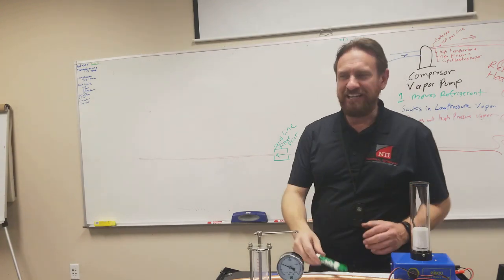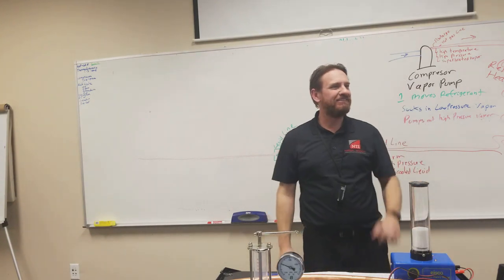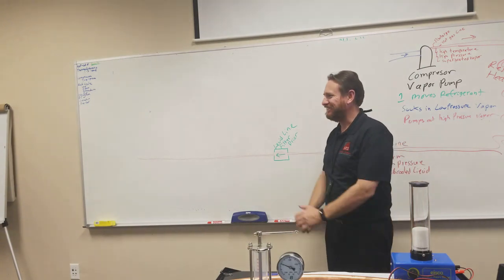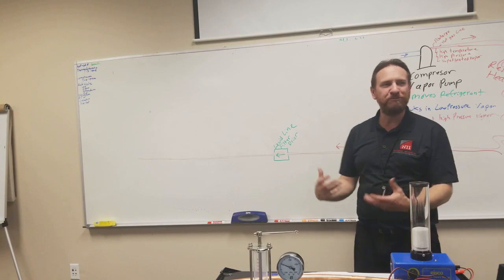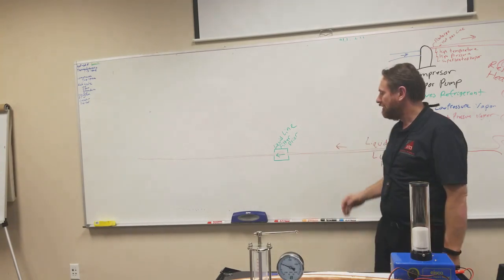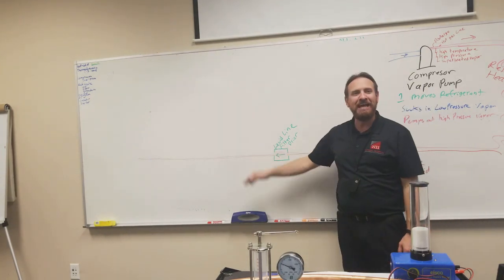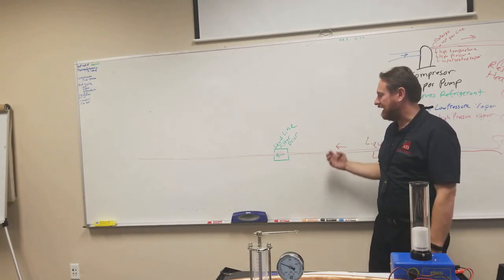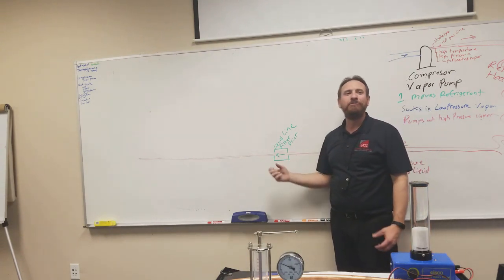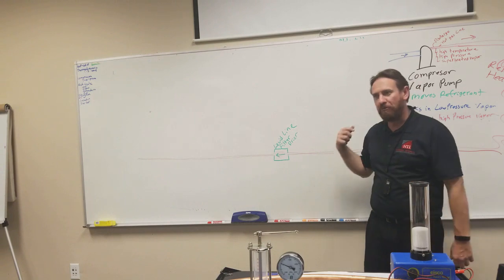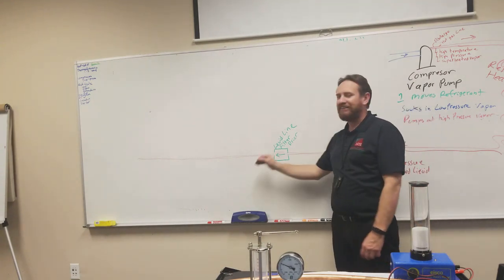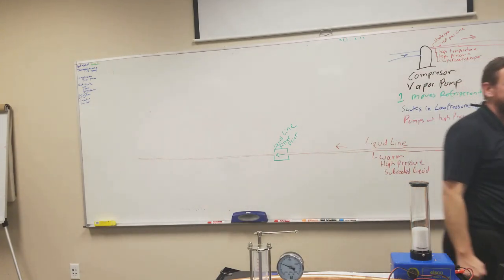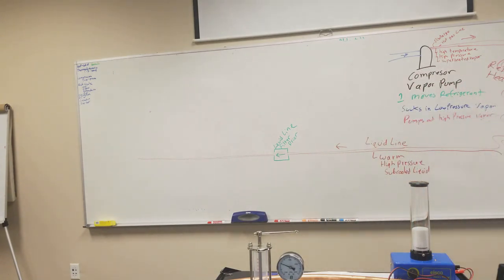Has anybody ordered anything and gotten those little packets in there that say do not eat? What's in that little packet that says do not eat? Silica gel or silicate dust, or a desiccant. What it does is absorb moisture. It absorbs H2O. So there's liquid refrigerant, it's not absorbing that. If there's any H2O, any water in there, ideally that will absorb and hold that water so that water's not running through the entire system. It also has a filter effect in there, so it's taking some contaminants out of that unit, helping filter it. So I've got that to pass around so you guys can see it.